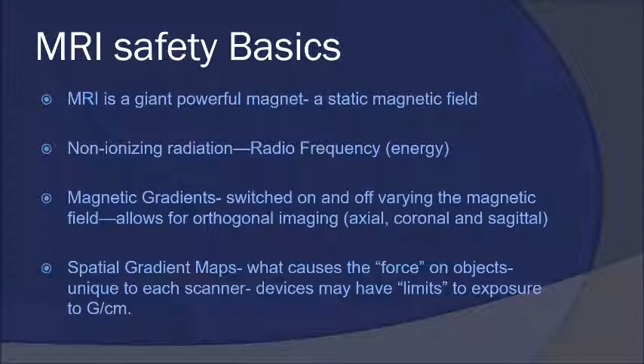And then we have spatial gradient maps for each scanner, and these are unique to that scanner. These are maps that demonstrate the greatest exposure of a specific device that can be exposed safely in that area. So please understand this. This is determined by the location of that specific device in a specific patient for a specific scanner. The spatial gradient is strongest near the ends or the openings of the magnet and decreases with distance. And also at isocenter is that of very minimal exposure. It's still there, but it is minimal, it is less.